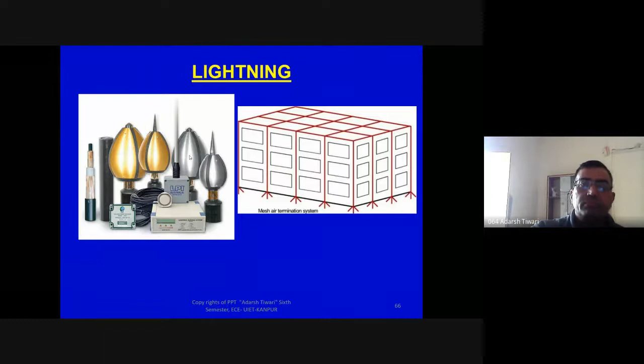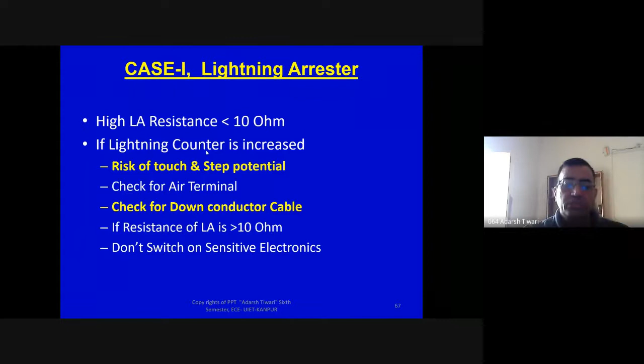So we have to check the air terminal, whether it is burnt or whether it is safe. After that strike, we have to check all the ground conductors, and if the ground resistance is more than 10 ohm, we have to change the earth terminal.